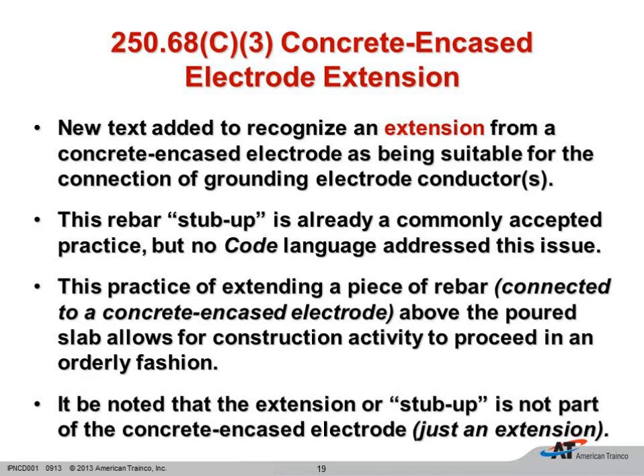And so the National Electrical Code wanted to address that because it was common work practice out in the trade. What they wanted to make sure that we understood was this is just an extension from a concrete encased electrode. And so the electrode itself is all of the rebar that's joined together in that slab or foundation. It's all that rebar, and all we're going to have is an extension coming up somewhere that we can either CAD weld to or pressure connect to, however we want to make that connection. But all of our grounding electrodes at any facility have to be tied together. So if we're thinking about metal water pipe, building steel, and the rebar, we would bond all those together and then bring them back to the service with our grounding electrode conductor. So new terminology in the National Electrical Code about that.